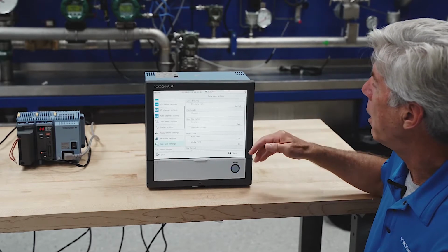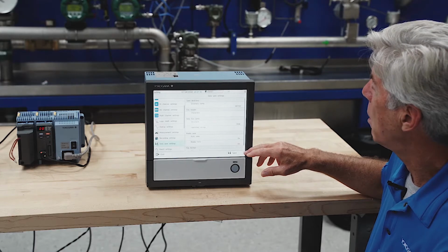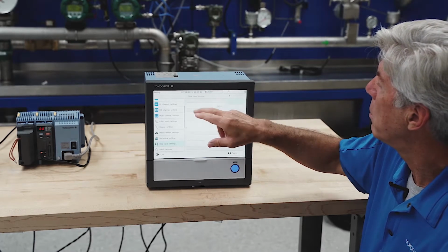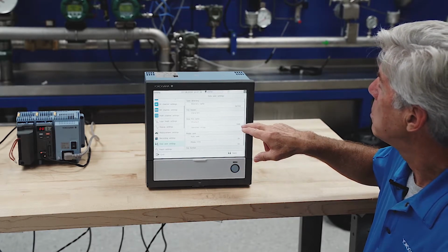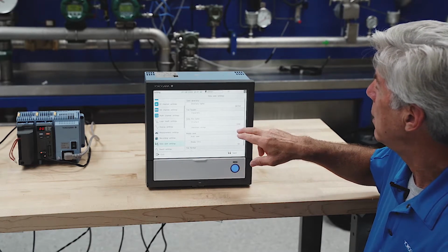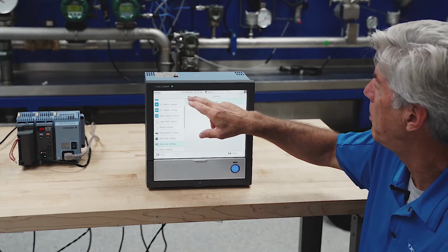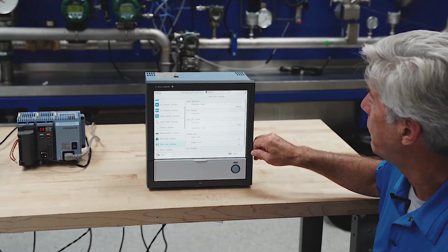Now we get down to the data save settings. This is the directory all the data is going to go into. If you've got multi-batch or batch turned on in the recorder, you can have not only the date and the serial number, but a linear number, and you can also have the batch name included as part of the data file. That's a real nice thing to have. If I have multi-batch, I always choose the batch name to be part of the data file. It makes it a lot more intuitive when you're looking over hundreds of files.